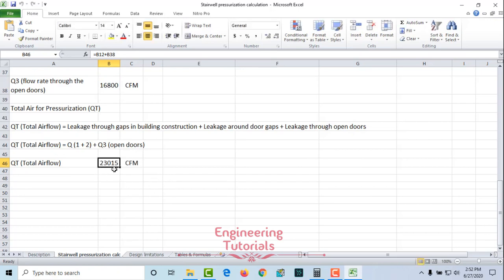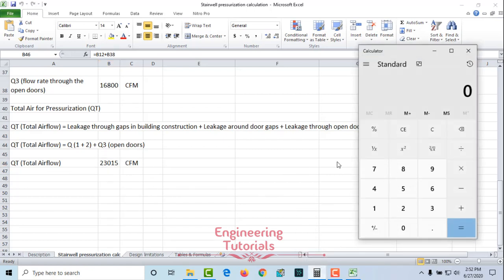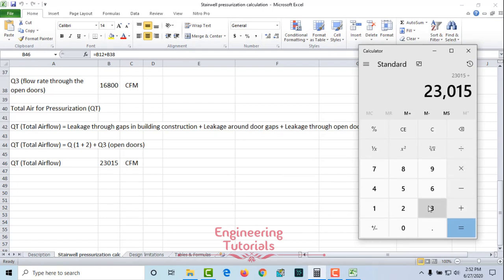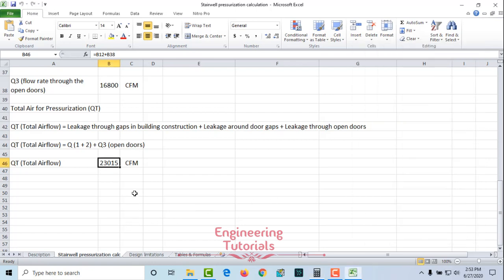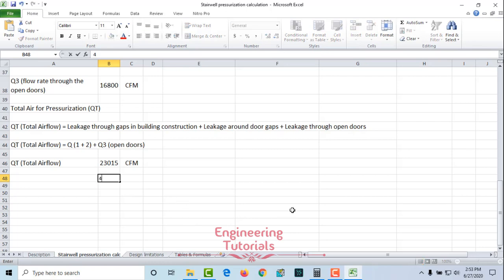Total volumetric flow rate for the stairwell pressurization system is Q1 + Q2 + Q3 = 6,215 + 16,800 = 23,015 CFM for five floors. For each floor, the required flow rate is 23,000 ÷ 5 = 4,603 CFM per floor.